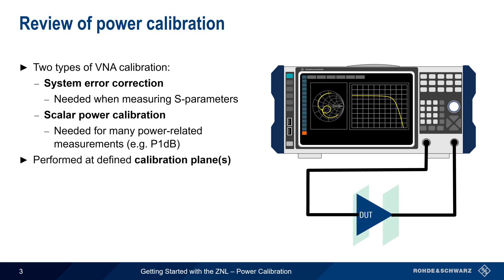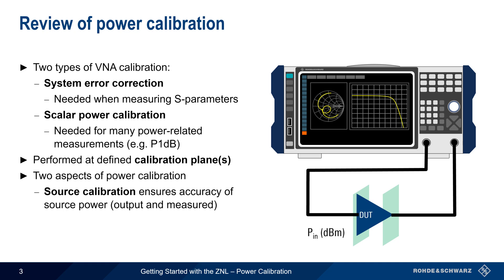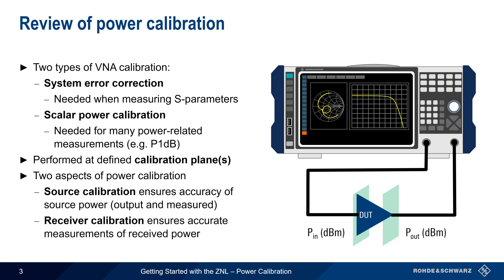Like system error correction, power calibration is performed at defined calibration planes, and thus can correct for loss, gain, or frequency dependencies in the test setup. There are two general types of power calibration. Source calibration ensures the accuracy of both the source or stimulus power, as well as the accuracy of the measurement of that power. Receiver calibration, on the other hand, ensures that the received power is being accurately measured.